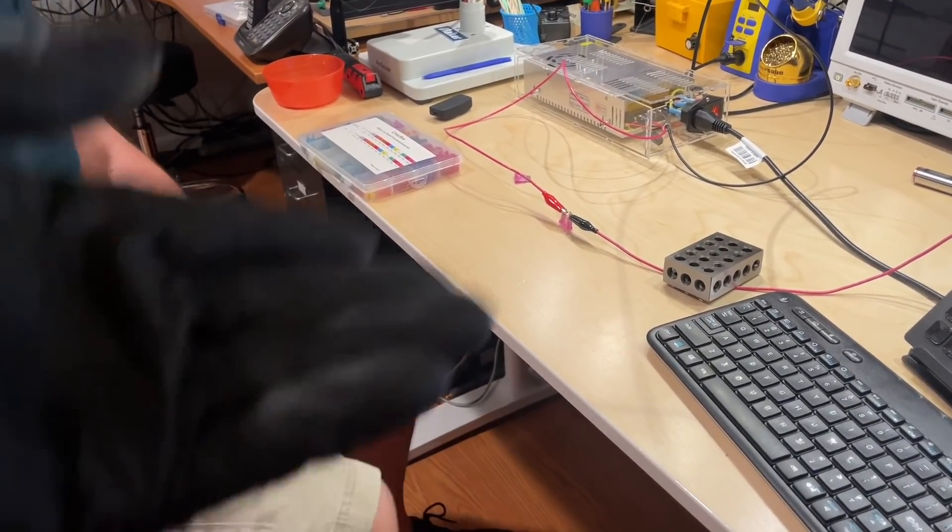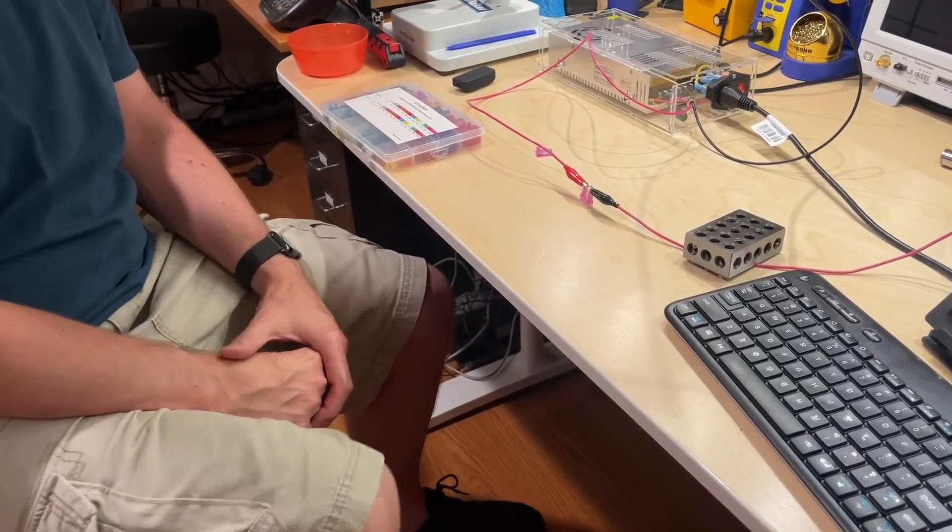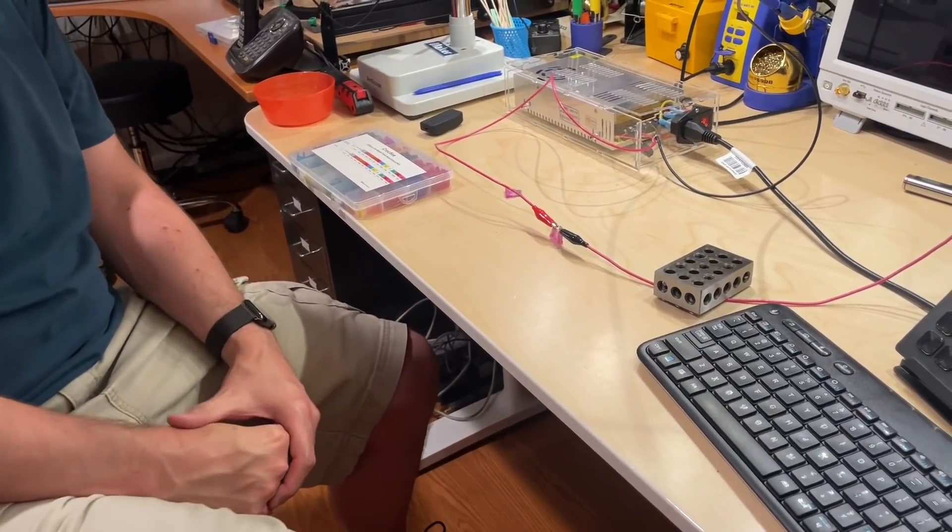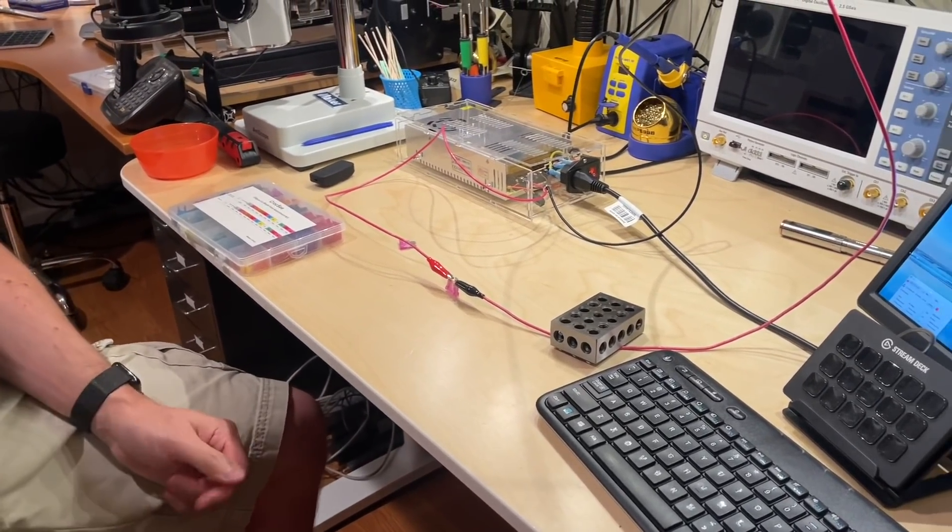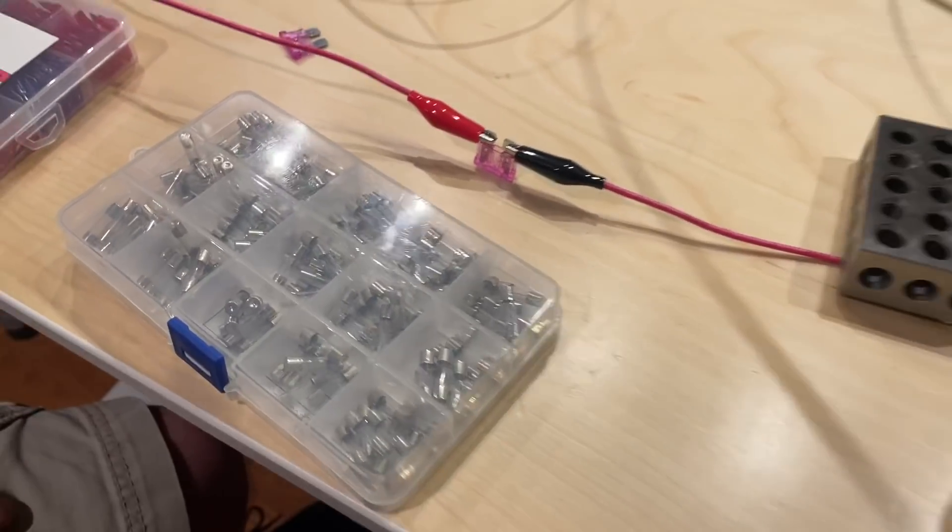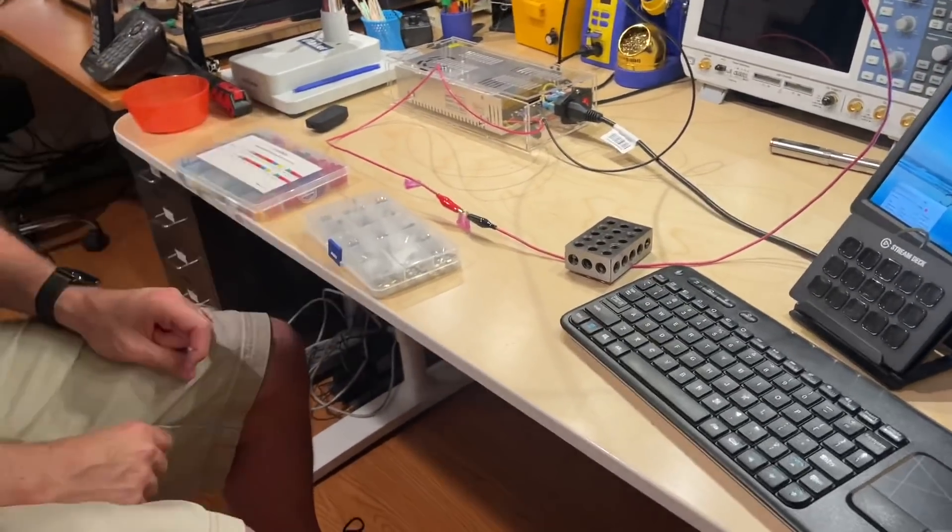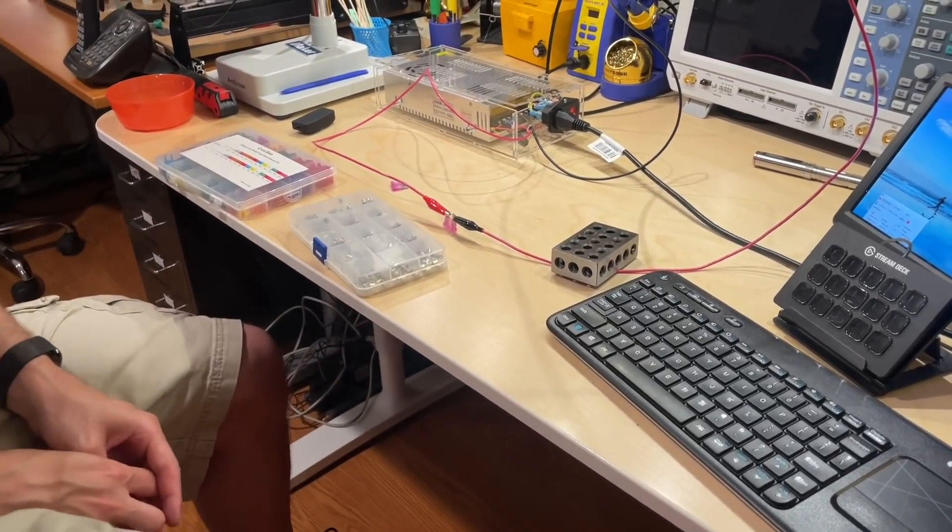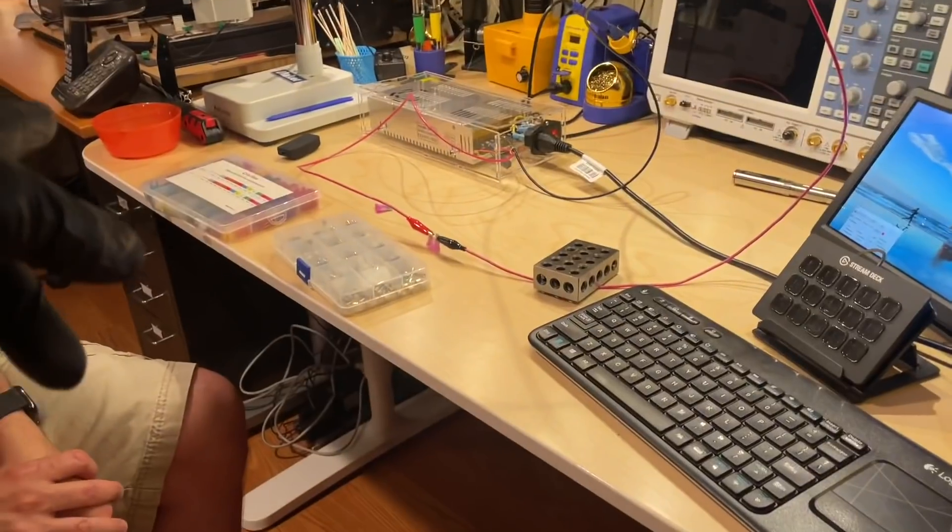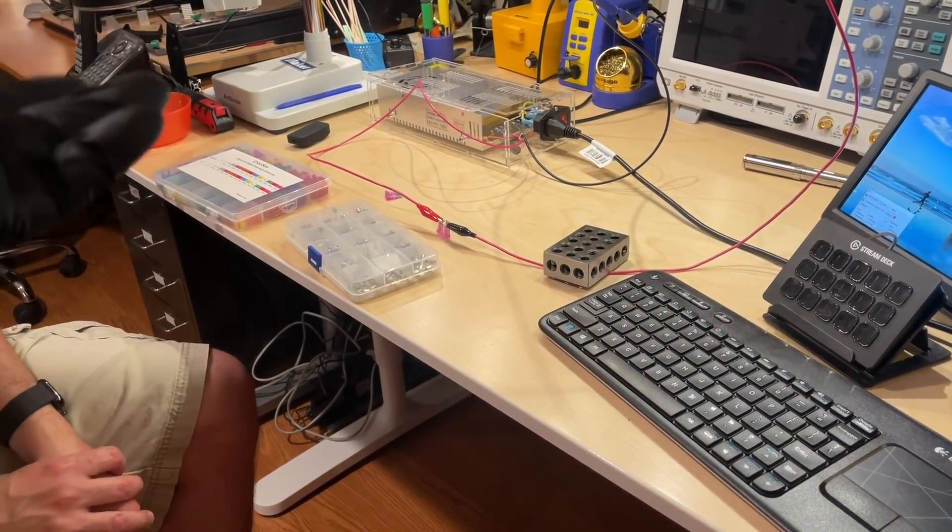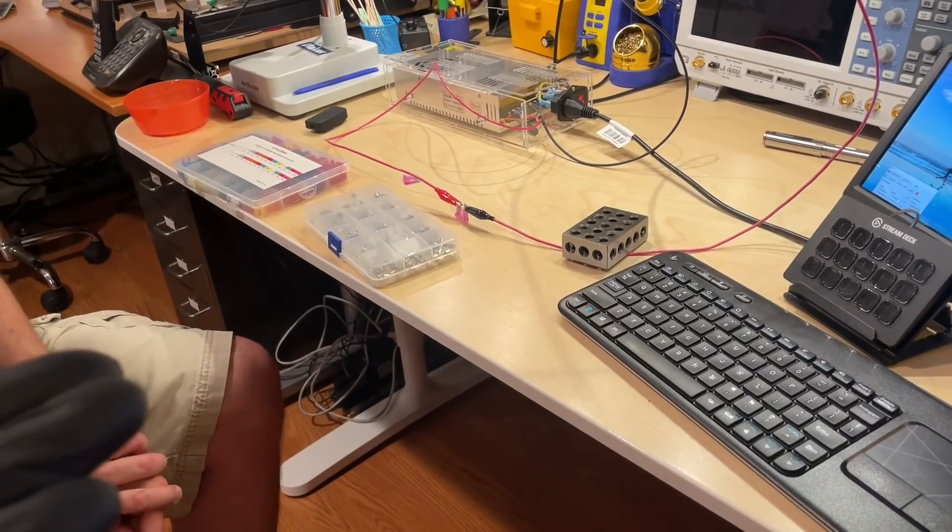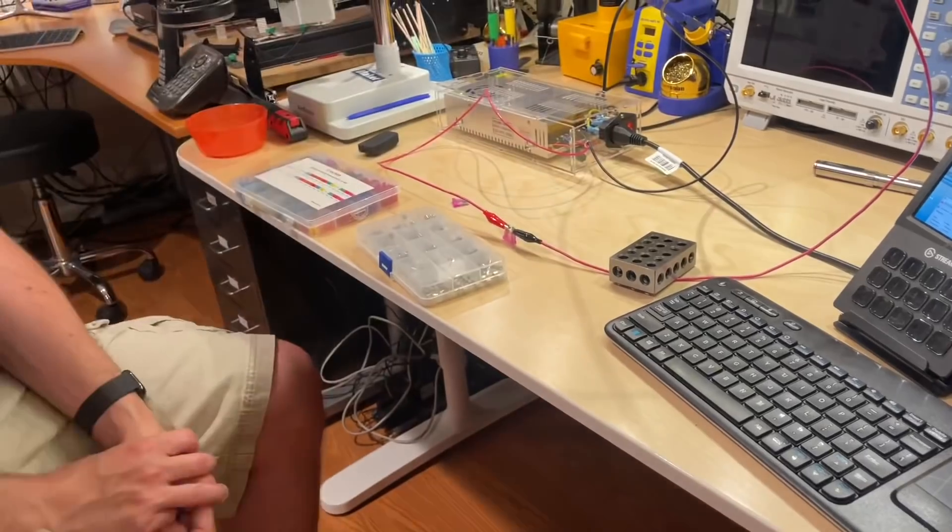In troubleshooting for a short in most air conditioning cases, you have a thermostat that's crossed over somewhere or the contactor is shorted out and you're getting significantly more than 24 volts on low voltage control wire. But I guess if it's just a little bit too much it could take a long time to blow. I tried these little glass ones too - I put a 5 amp in there, ran 10 amps through it, and it took over a minute and glowed like a light bulb.